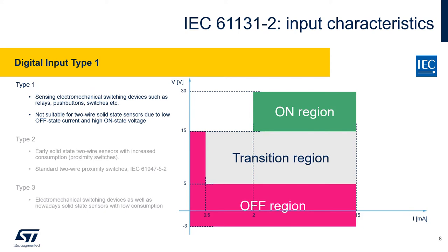Each characteristic type is suitable for a different kind of switching device. For instance, type 1 has been defined to suit ideally to electromechanical switching devices like relays, push buttons, or switches. It may not fit to two-wire solid-state sensors, because its transition region starts at quite low current, already at 0.5mA, and the on-region requires quite high voltage, at least 15V.